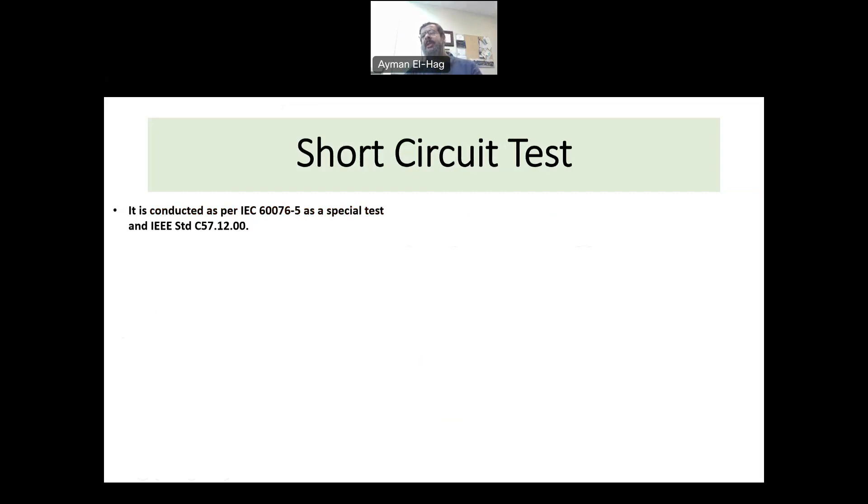Now, this short circuit test is different than the classical routine short circuit test that we conduct to find the losses, the copper losses, and the short circuit impedance. In that test, we apply rated current but very small voltage. But the short circuit test here is to test the ability of the transformer to handle a fault in the network.